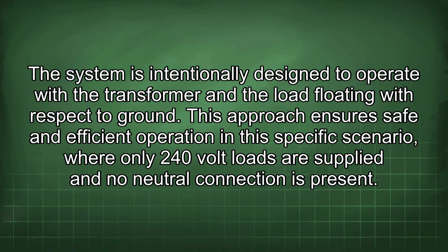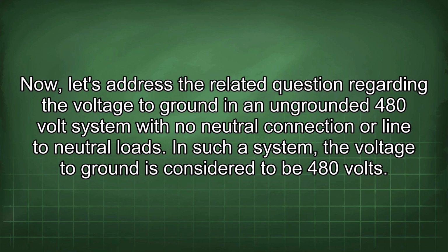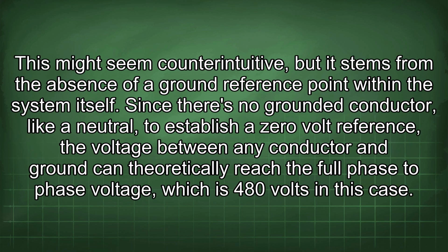Now let's address the related question regarding the voltage to ground in an ungrounded 480 volt system with no neutral connection or line to neutral loads. In such a system, the voltage to ground is considered to be 480 volts. This might seem counterintuitive, but it stems from the absence of a ground reference point within the system itself. Since there's no grounded conductor, like a neutral, to establish a 0 volt reference, the voltage between any conductor and ground can theoretically reach the full phase-to-phase voltage, which is 480 volts in this case.